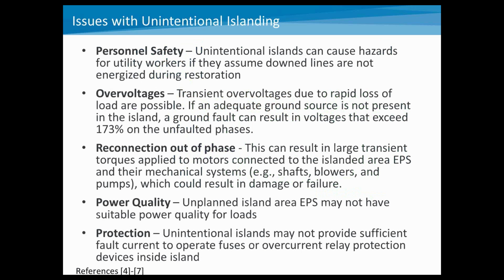And so what are the issues with unintentional or non-planned islands? First off, personnel safety. Unintentional islands, if they're operating, could cause hazards for utility workers if they're assuming that the power lines are not energized, for example, during restoration. So if you have distributed generation that is accidentally maintaining the power and voltage live on lines, that's a potential safety hazard. There's also the potential for overvoltage, both transient overvoltages due to the rapid loss of load. If a breaker opens and you have generation on the islanded side, you may have a very quick overvoltage condition occur because of the loss of load on that.